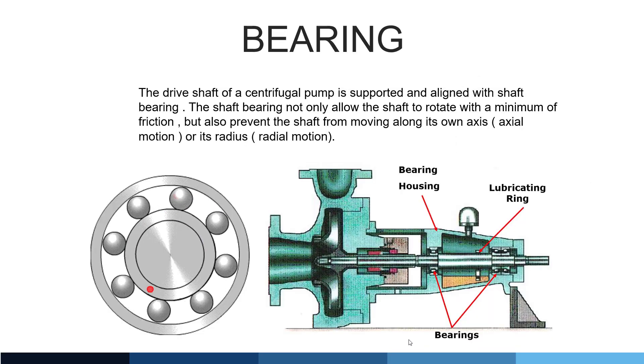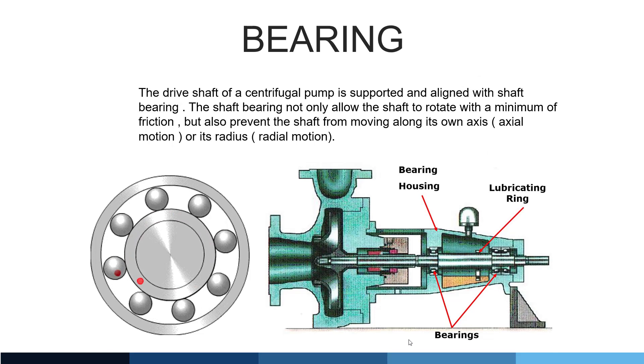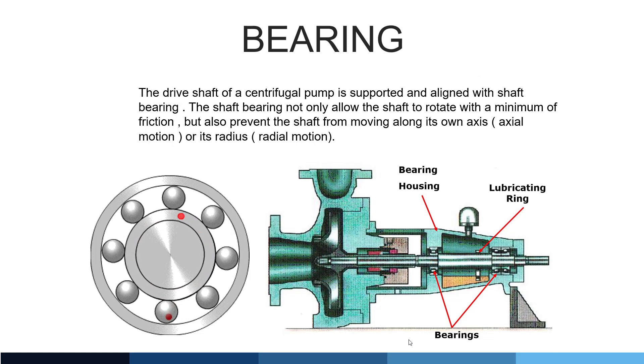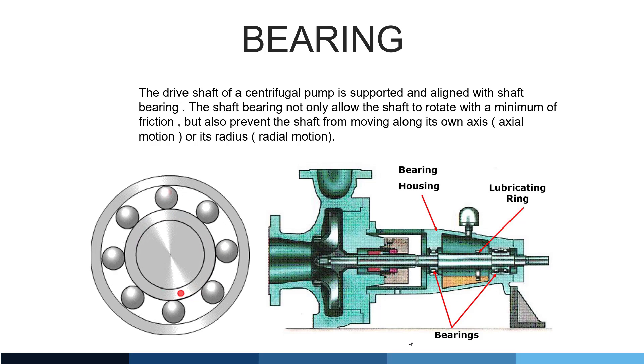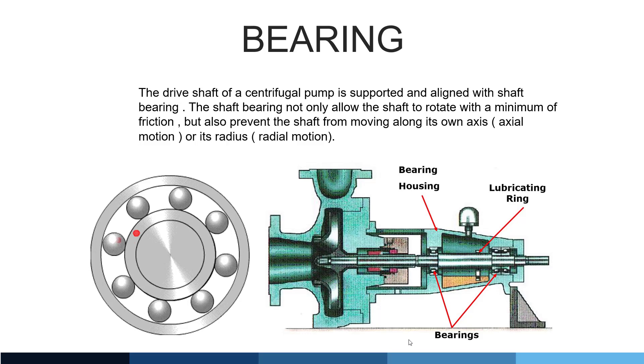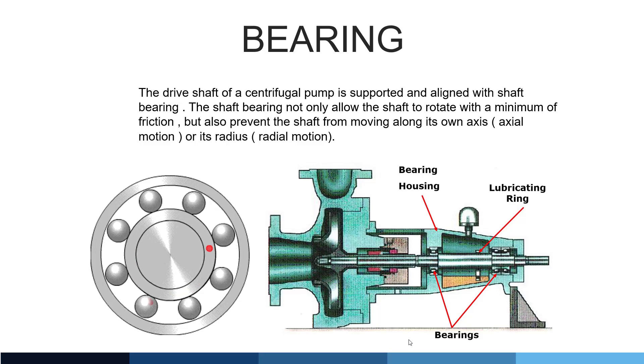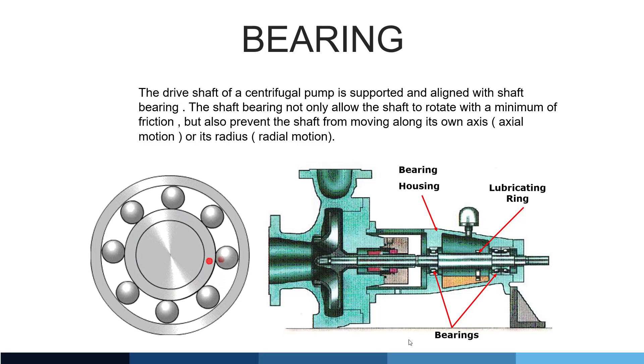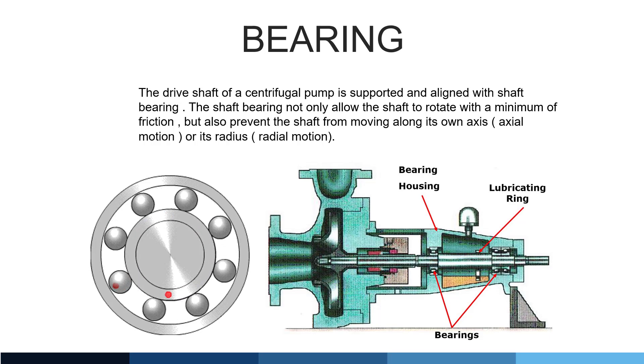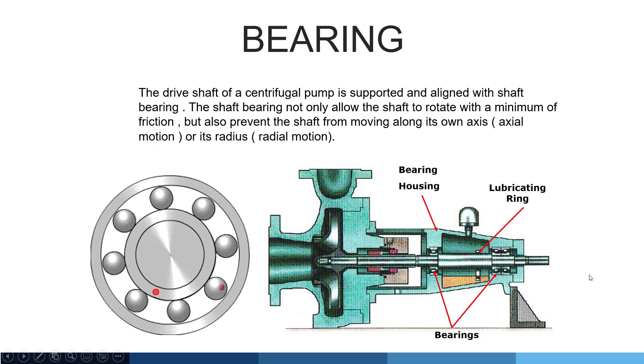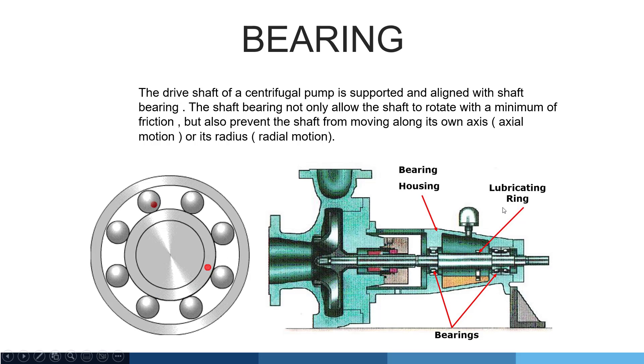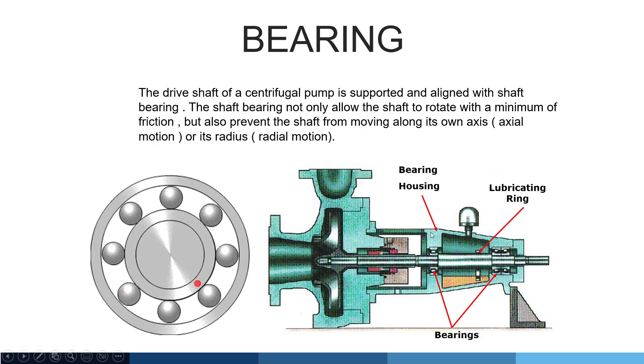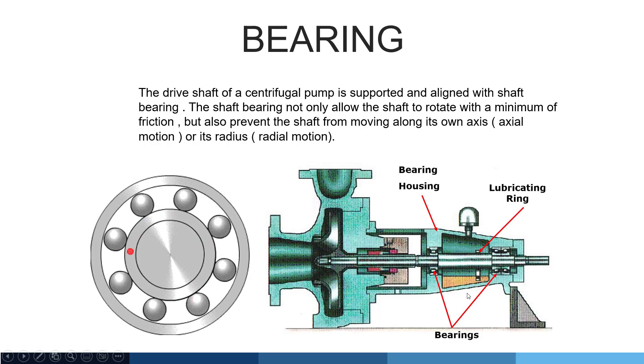Bearing. The drive shaft of the centrifugal pump is supported and aligned by the shaft bearings. The shaft bearings not only allow the shaft to rotate with minimum friction but also prevent the shaft from moving along its own axis or radius — that means axial and radial motions are controlled by the bearings. You can see the bearings in these pictures, including the lubrication ring and bearing housing.